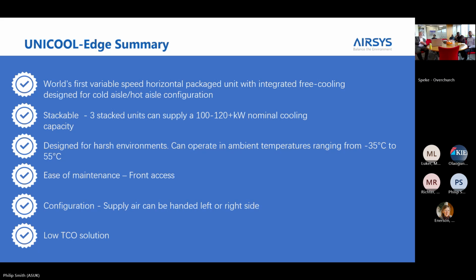So this sort of product was originally developed in the United States. It'll work up to 50+ degrees C. It'll work down to -35, and at all points in between. Obviously, it's not going to give you fresh air free cooling at 55 Celsius, but the refrigerant will still run as it will down at -35.